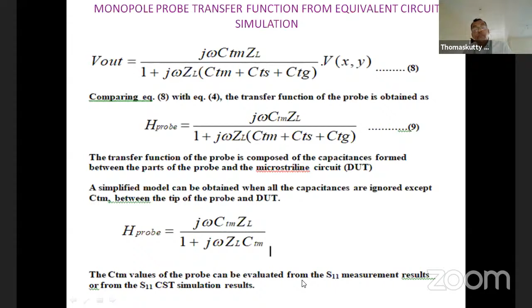Now we are putting the probe over a microstrip line. This is very important in calibration. Most of these small near field probes, we can use this for calibrating. Once you create a probe, it has to be calibrated. For that, you know the field at 1 millimeter above the microstrip line, and you measure this, and with that, one of the methods for probe calibration is this one. You put it over the microstrip line, and with that you can calibrate.